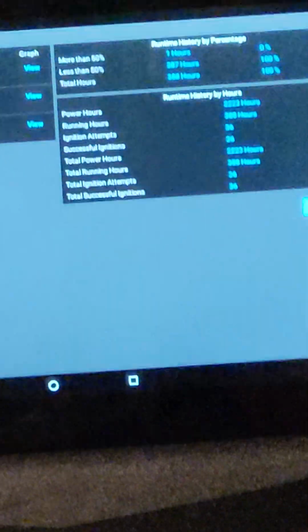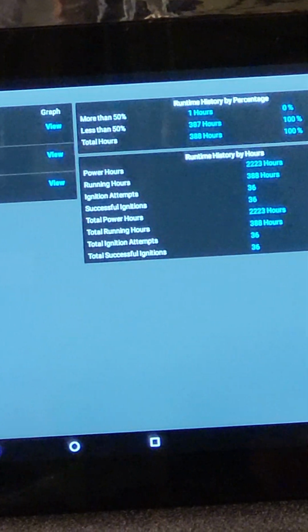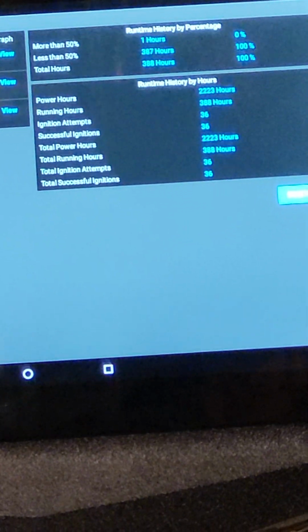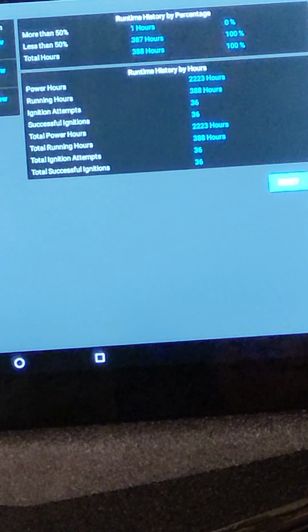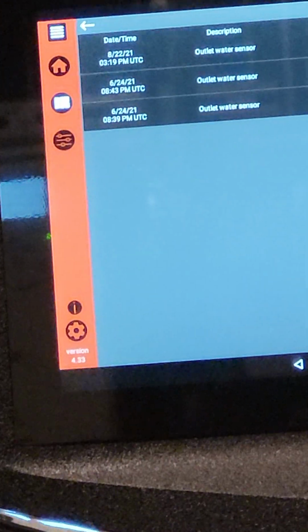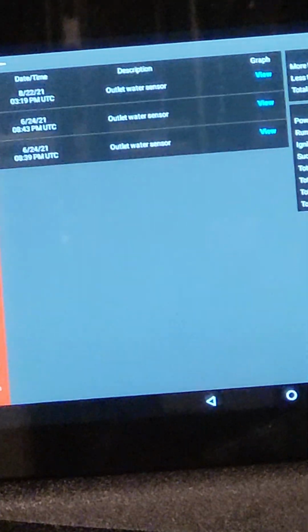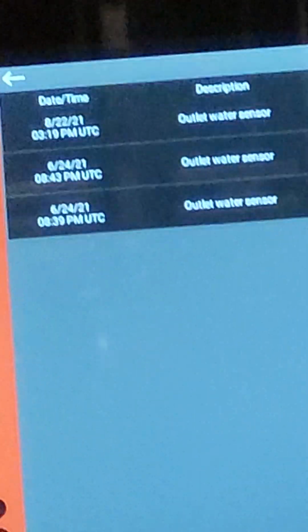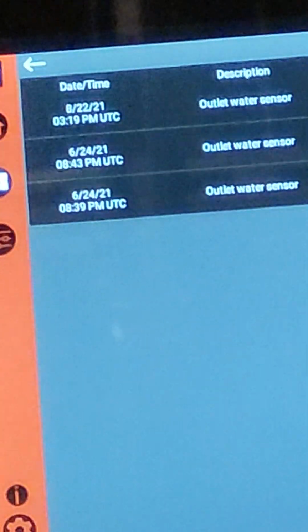History, it's one of my favorite screens. If you just tap in, the history will show you every alarm you've ever had. Well, the last 20 alarms you've had, but it'll show you what alarm and it'll give you a date and time stamp. So you know exactly what happened. If you come in the morning and this is locked out, you can see exactly when it happened. And again, we tell you what the alarm is. Outlet water sensor. These were from startup.